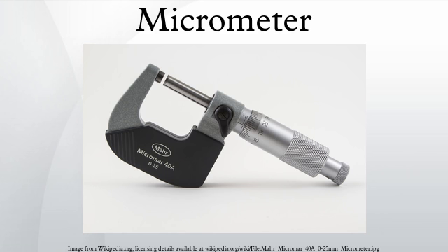Because the definition of the meter is now based on a light wavelength, the international prototype meter is not quite as indispensable as it once was. But such master gauges are still important for calibrating and certifying metrological equipment. Equipment described as NIST traceable means that its comparison against master gauges, and their comparison against others, can be traced back through a chain of documentation to equipment in the NIST labs. Maintaining this degree of traceability requires some expense, which is why NIST traceable equipment is more expensive than non-NIST traceable. But applications needing the highest degree of quality control mandate the cost adjustment.